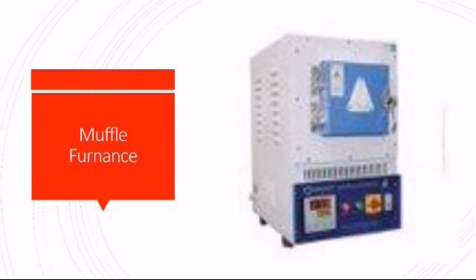Today, a muffle furnace is usually a front-loading box-type oven or kiln for high-temperature applications such as fusing glass, creating enamel coatings, ceramics, and soldering and brazing articles. In ceramics, muffle kilns were typically used for relatively low temperatures, for overglaze decoration. They are also used in many research facilities, for example by chemists in order to determine what proportion of a sample is non-combustible and non-volatile, i.e., ash. Some models incorporate programmable digital controllers, allowing automatic execution of ramping, soaking, and sintering steps.